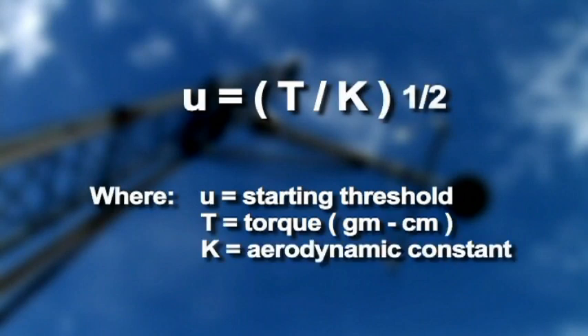The EPA QA Handbook on Meteorological Measurements, section 2.5.1.1, has the equation for converting torque to meters per second. Reference your manufacturer's manual for the optimal starting threshold for your sensor. If the starting threshold is above the manufacturer's recommended value, then the bearing must be replaced. Retest the torque after you have replaced the bearing. This now concludes the wind speed anemometer calibration.